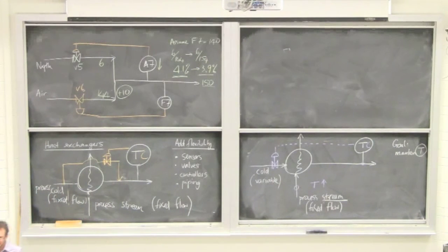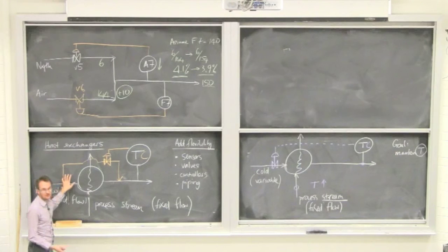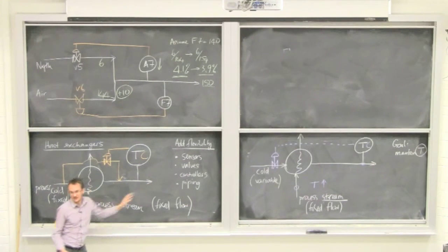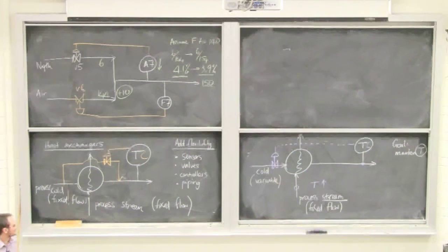But an interesting idea is we do see that in some heat exchangers, that level is the mechanism to control the temperature. So coming back to this one, that is the desirable way to control this temperature when you cannot vary the flow. Putting a bypass around it does not alter the flow coming in or the net flow leaving. The bypasses connect and the total flows recombine again. So total flow doesn't change.